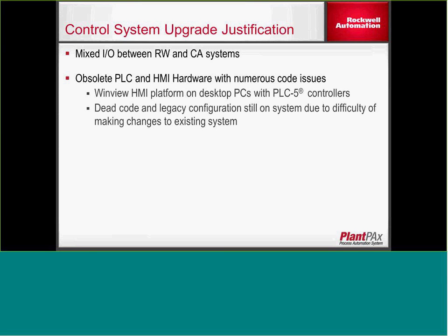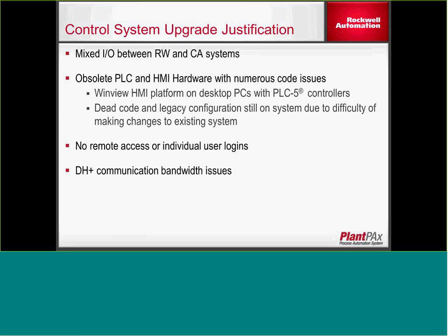The controls hardware was obsolete — a Winview HMI platform and PLC-5 controllers — and there was a lot of dead code from the legacy system, which made it difficult to troubleshoot and maintain. There was no remote access or individual user logins because of the old Winview HMI application. There were also limitations around their DH Plus network. The system spanned several buildings and periodically they would have issues with remote racks dropping out, without good visibility into the system for timely troubleshooting. They also wanted to move remote I/O racks out of the MCCs with 480-volt power into lower-voltage 120-volt or below panels.